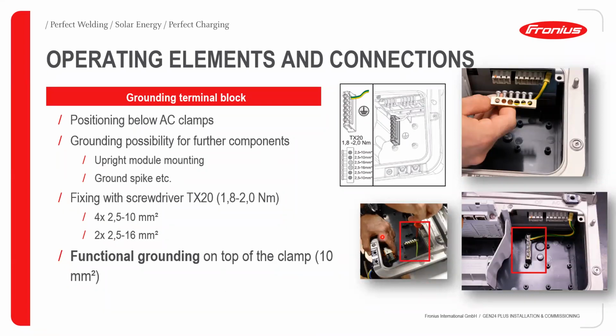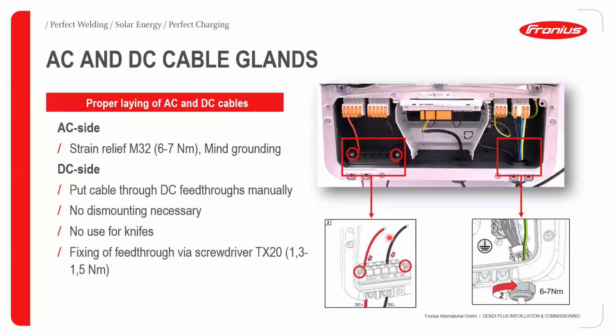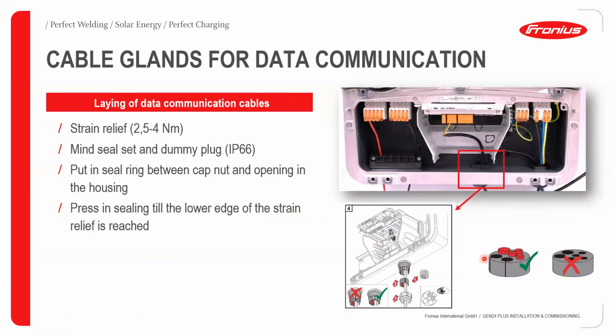Great. So these are just basically the dimensions of our connection points and terminals. Yeah, same thing here. Of course, also the same thing here. But what I would like to stress here is that once you're connecting your communication cable, please ensure that you pop out only the opening meant for the particular communication cable that you want to connect. Ensure that you don't pop out more than necessary, because it will reduce the IP protection of the inverter. So if you just need two communication cables to be connected, just pop out two as indicated here and then connect.